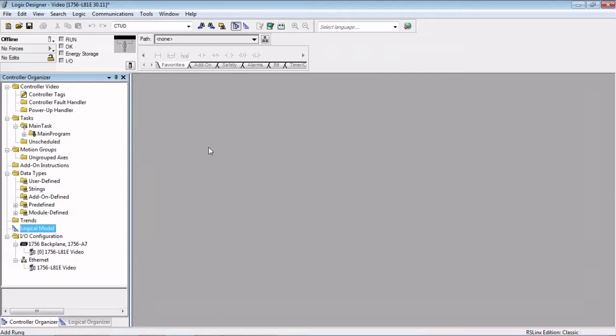What an AOP does is it allows you to add a device on a network without having to write a bunch of message instructions and sequence to do the read and write to that device over the network. All that programming has been done for you underneath the hood. These AOPs are available for a lot of Rockwell products that are on networks and a lot of Encompass partner products that are available on network as well.